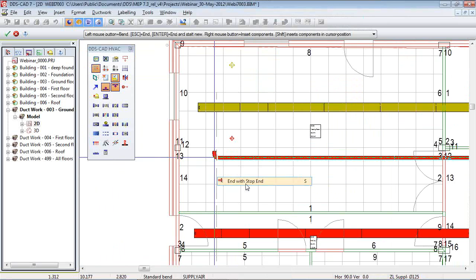So I would like to have a small part coming out in this case, and I can use different materials. So from rectangular duct I can also have a saddle to a round duct. So I can say I would like to have 125 round duct, and then the round duct is coming from here, from the saddle, and can end somewhere here with the stop end.